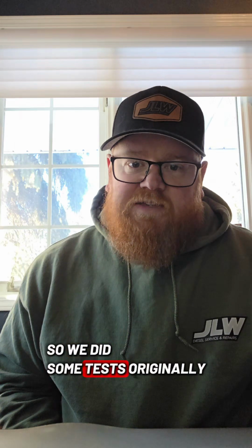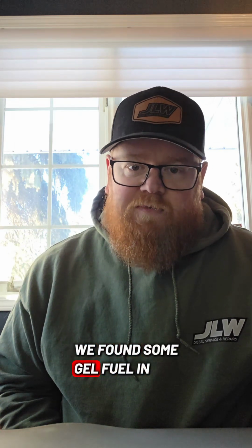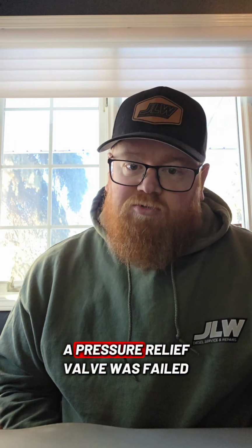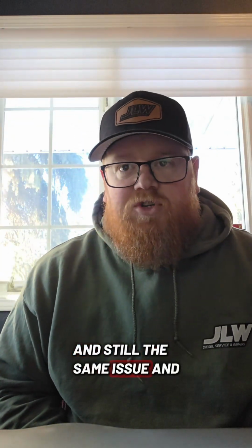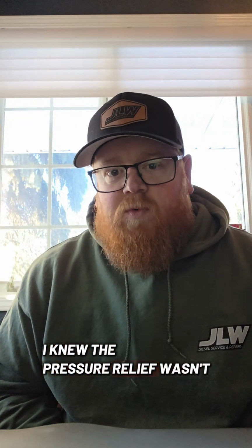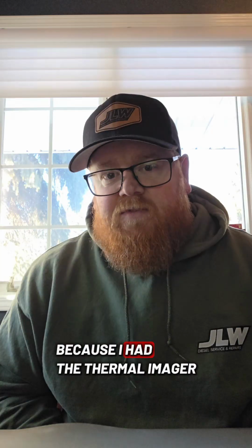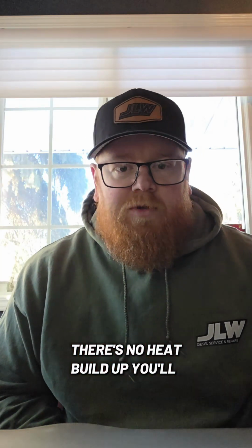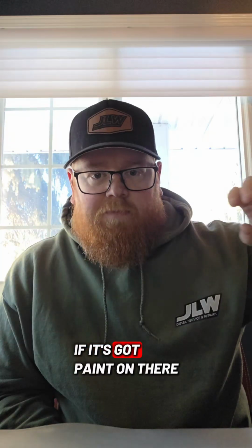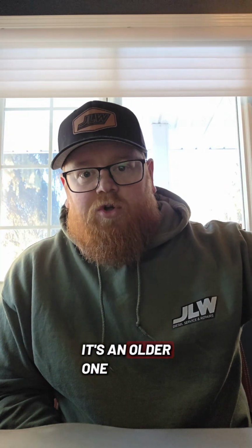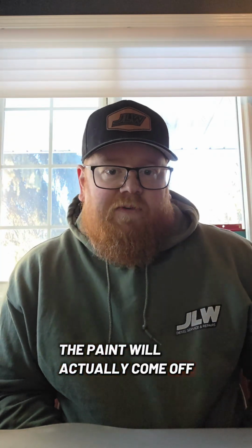So we did some tests. Originally we found some gel fuel in a pressure relief valve that was failed, so we replaced them, and still the same issue. I knew the pressure relief wasn't leaking again because I had the thermal imager on. There's no heat build up. You'll see that it actually builds up heat. Another way you can check is if it's got paint on there. If it's a new one, if it's an older one, the paint will actually come off if it's leaking so bad because of the heat.